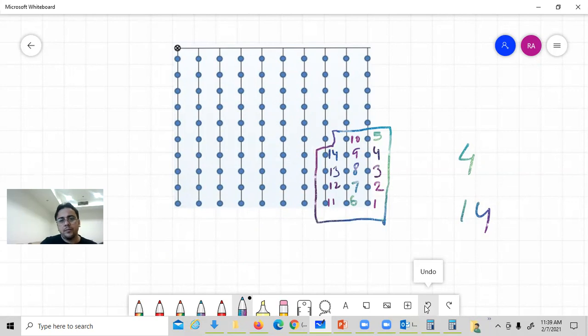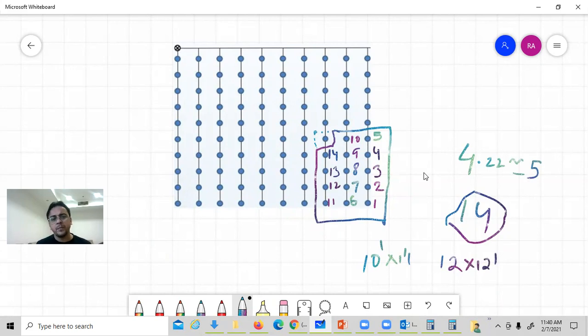Although it is not a perfect rectangle, we can say that the last leg of the rectangular, these areas can get water at full pressure and flow. This is the hydraulic design area based on this project. We just used the formulas and we got to the point that 4.22, we have to consider the next value to 5 and total we need 14. The number of sprinklers in hydraulic design area looks a little bit high because the spacing is only 10 feet by 11 feet. If we had increased these values to like 12 feet by 12 feet, which is acceptable by NFPA, we can reduce our sprinkler further.